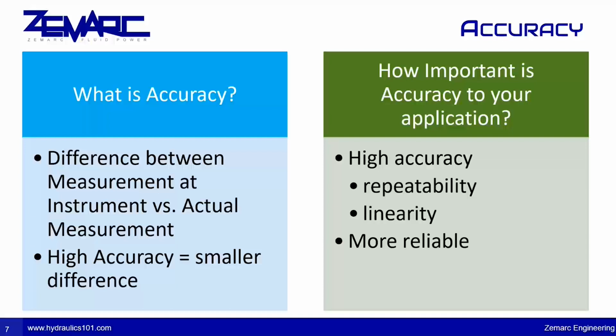Repeatability is also an important factor in many applications, and this refers to the ability of an instrument to produce consistent measurements when the same quantity is measured multiple times. High repeatability is desirable because it increases the confidence in the measured values and reduces the need for repeated measurements. Linearity is another important factor, especially in control systems and automation applications. It refers to the degree to which the instrument's output responds linearly to changes in the input. A linear feedback system is easier to program and control, and it provides more precise and predictable results.